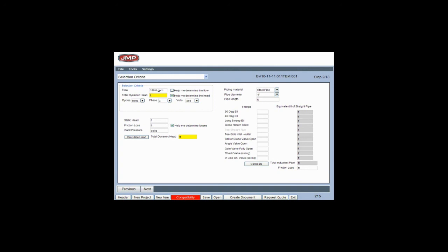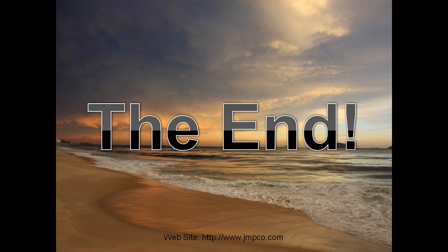Straight pipe, four inch, and it'll calculate the pressure drop for you. On the left hand side, we got the static head, which was a 28-foot lift. We got the back pressure, which was at 19.7 feet. I think you quickly see, we can put everything in this online selection tool from Bell & Gossett, and it will give you the pump head, and it gives you a permanent record of it, and you do need to calculate it. This is one you don't guess it. You make sure you calculate this.